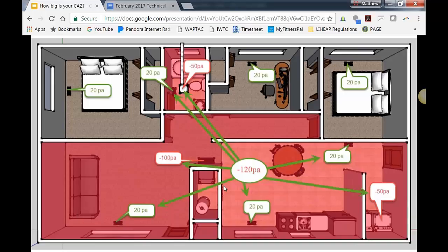Again, just to emphasize that, if you see that situation, once you close that bedroom door and that bedroom has a supply run in it, and that big hole to the outside, which in this case was the swamp cooler, it will cause a serious depressurization, because now you've got all of the supply air in that room, and a 6-inch run can easily be 150 CFM blowing directly to the outdoors. So just watch for those kinds of situations.